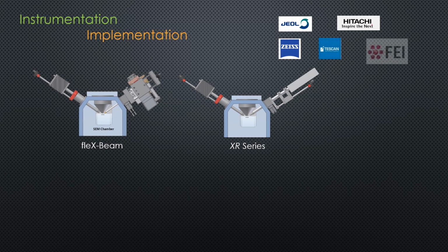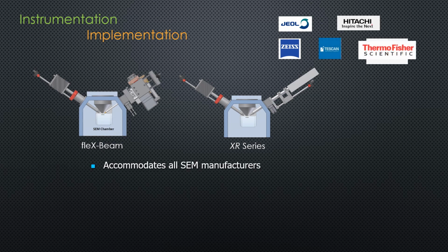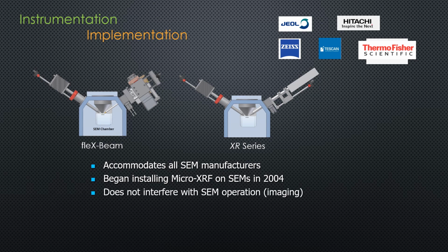I began developing adding XRF to the SEM in 2003. It wasn't until 2004 that we actually installed them. Once installed on your scanning electron microscope, nothing interferes with the basic SEM operation. Any EDS system can be used to collect the X-rays from your Micro XRF source. Now let's begin talking about the application itself.